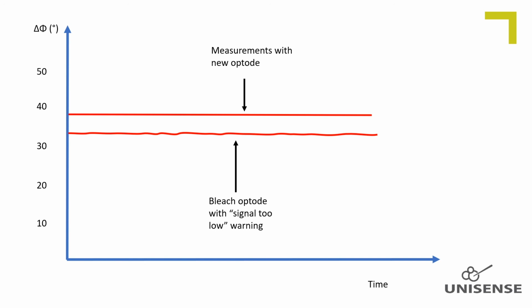The warning is triggered when the fluorescent intensity of the dye gets under a certain threshold. This does not mean that the optode no longer is sensitive to oxygen, but the calculation of the phase shift is statistically inaccurate. Measurements with such an optode are more noisy compared to a new optode, and the original resolution has been lost. It is, however, again up to the user to judge whether the optode could still be used or must be replaced. As mentioned before, the cost for shipping, reactivation and recoating the fiber is so high that we do not offer repairing bleached optodes.